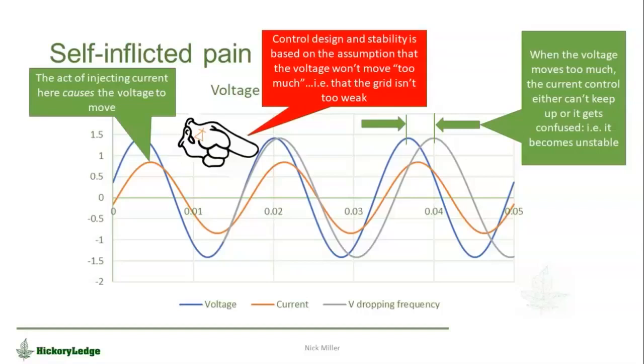Everything I'm going to talk about in the next several slides looks at the fact that that isn't really true. As the system gets progressively weaker, the action of injecting current actually causes the voltage to move, which means the presumption of the control—that the voltage is where it was measured or moving in a direction it anticipated—is in fact altered by the act of the control. In the limit, the stability limit, the action of current injection moves the voltage so much that the control does not have the desired outcome, and it can't keep up with the fact that the system is moving. That's how grid-following inverters go unstable.